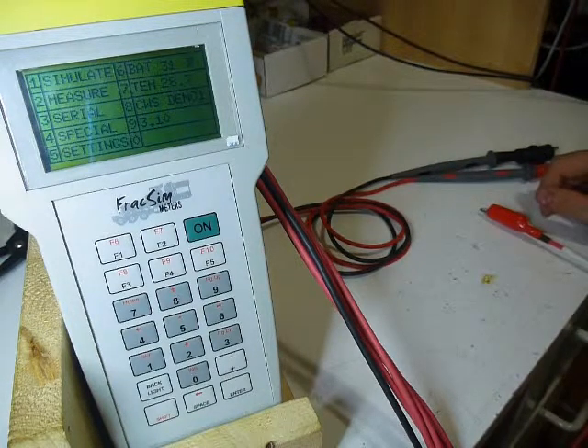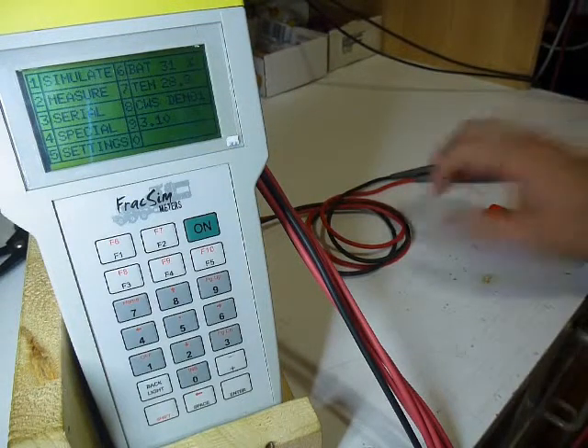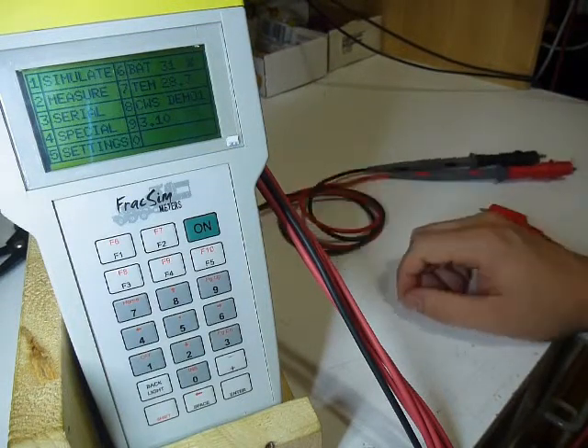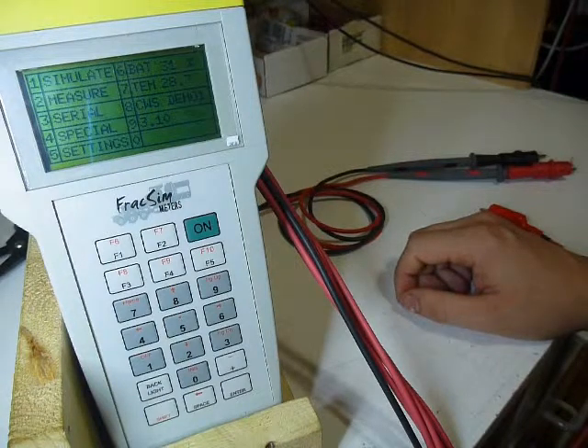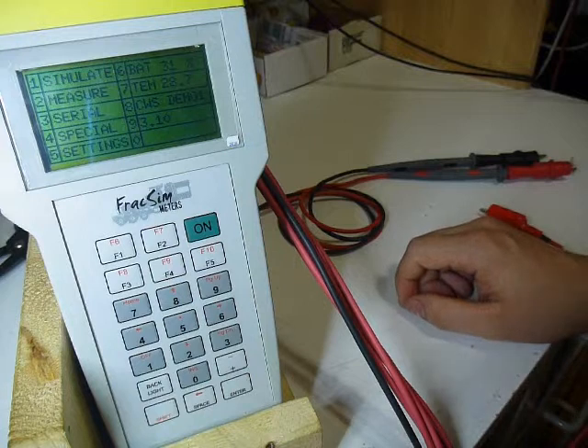The advantage of using that high impedance, with a polyfuse in series with a resistor, is I can get away with not having any fuses whatsoever. So this meter will never let you down. If you need to measure 4 to 20 milliamps, you cannot pop a fuse in it. There's no way, it'll always be there for you, ready to go.